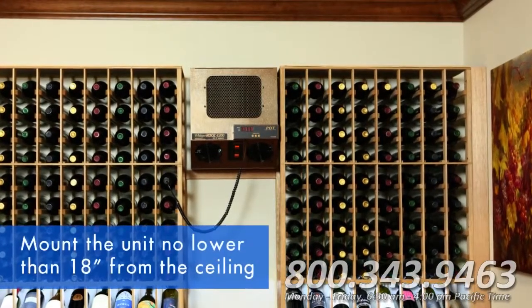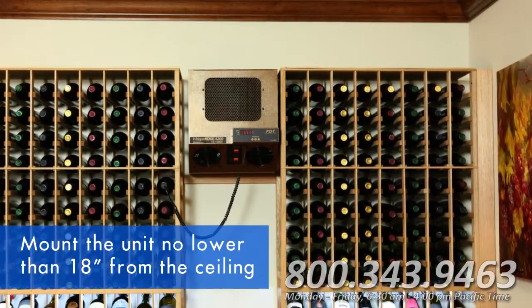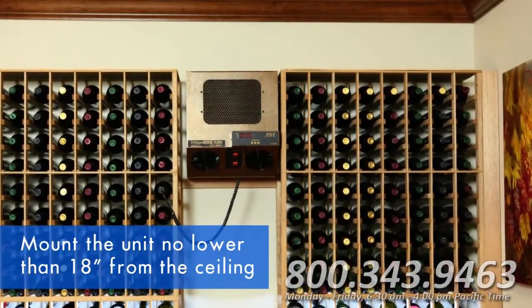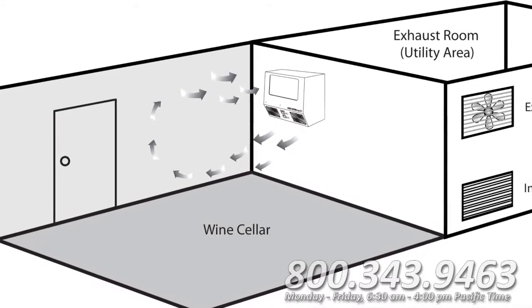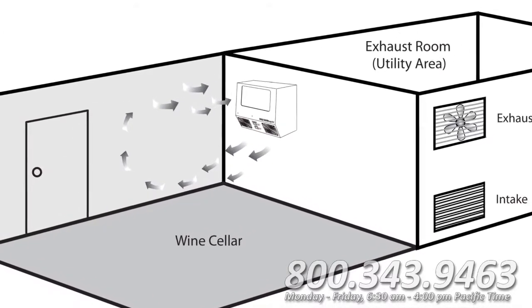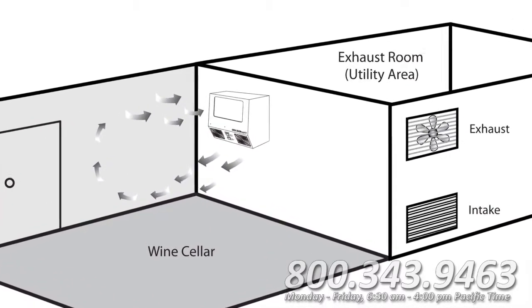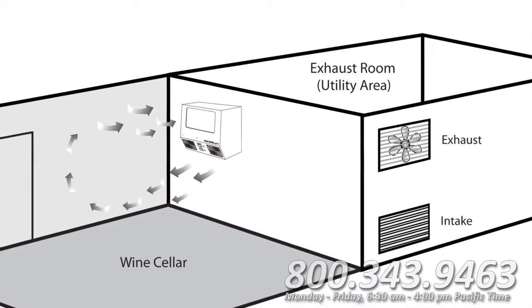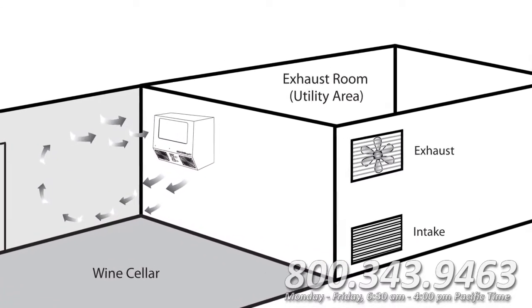Mount the unit no lower than 18 inches from the ceiling so that the unit can capture and cool the rising warm air in the cellar. The space that the unit exhausts to must be larger than the wine cellar, and for best practices, it should have an exhaust fan and a fresh air inlet for proper heat dissipation.